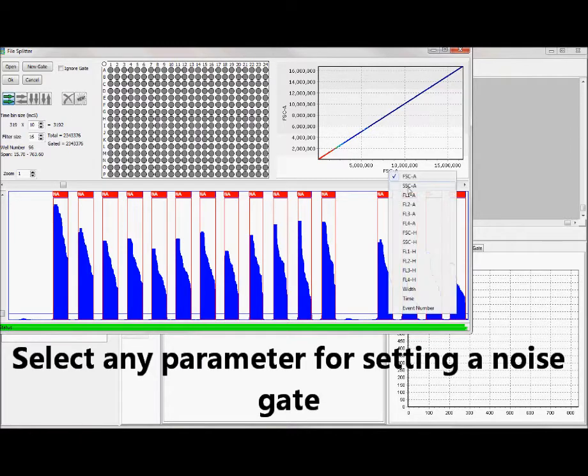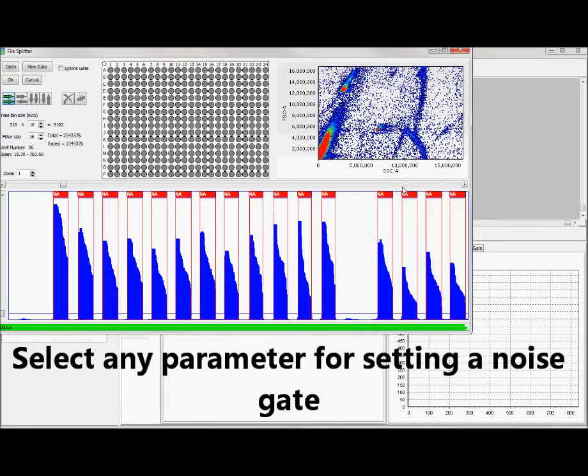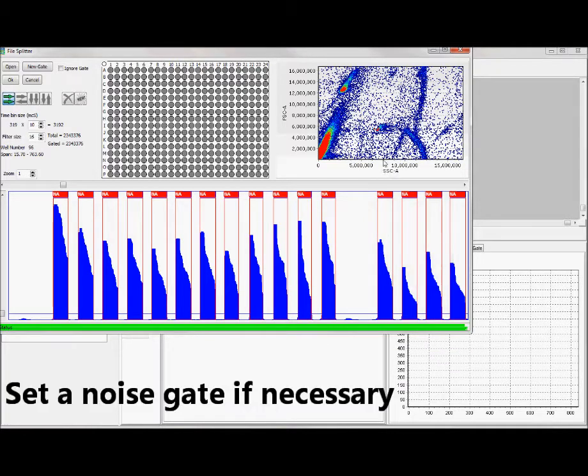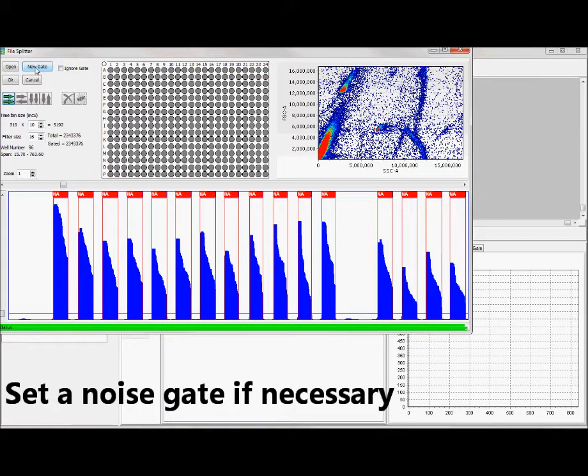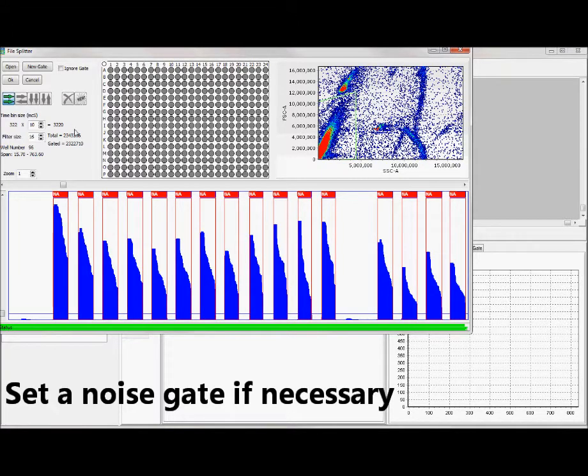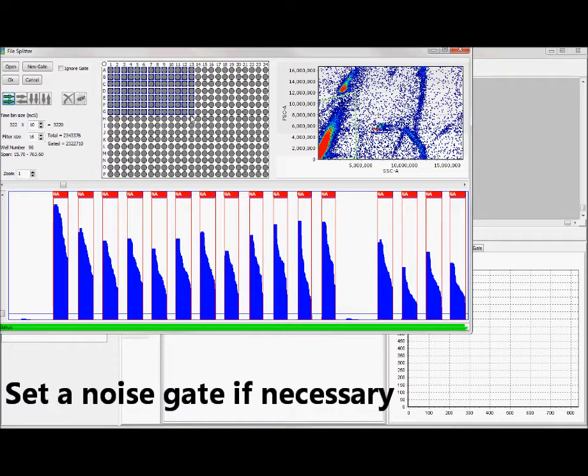I can now determine whether to set a noise gate or not. If I go here, you'll see that we have the forward scatter by side scatter, or if you wish to look at anything else you can. At this point you can make a choice of setting a gate. If you do, you would click new gate, and perhaps these are the real cells. We now create that gate. Once you've created that gate and you've told it that you need a 96-well plate...